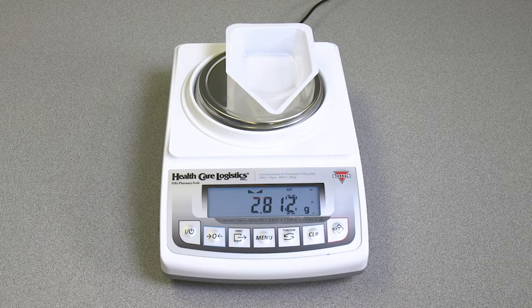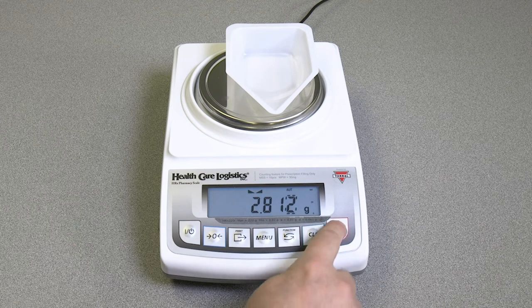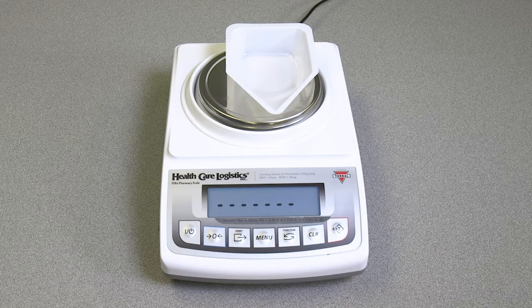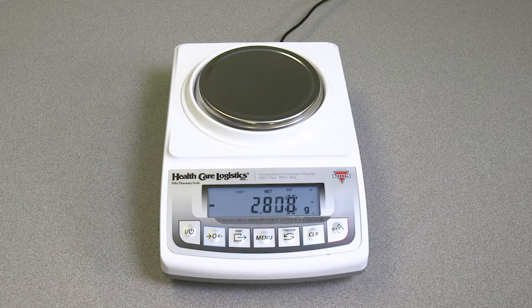To tare the container, press the T key. The display will show a dotted line indicating that the scale has begun the taring process. When the taring process is complete, the scale will return to weighing mode. The display will indicate 0 and the net indicator will be shown on the display, signaling that the next weight taken is a net result. When you remove the container, a negative weight will appear.